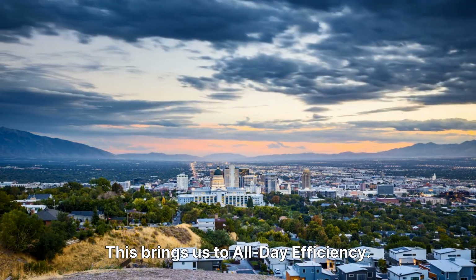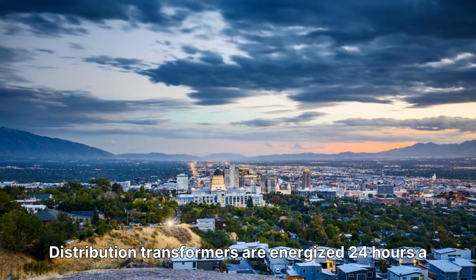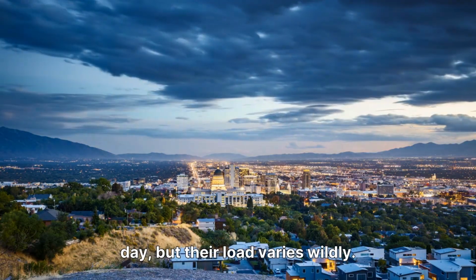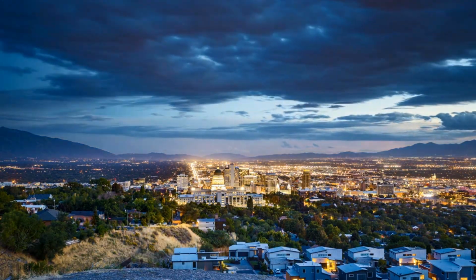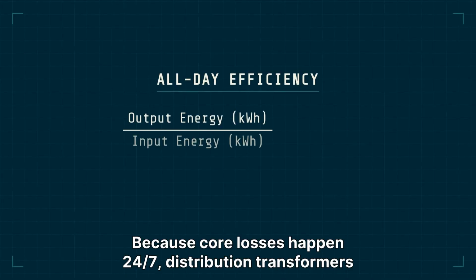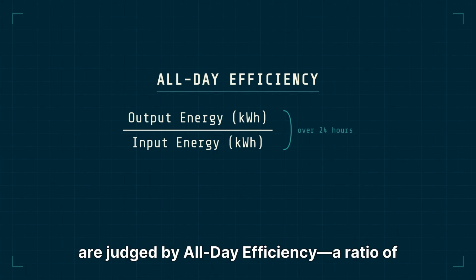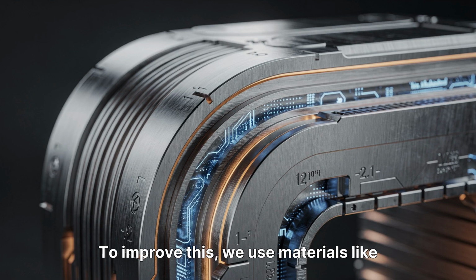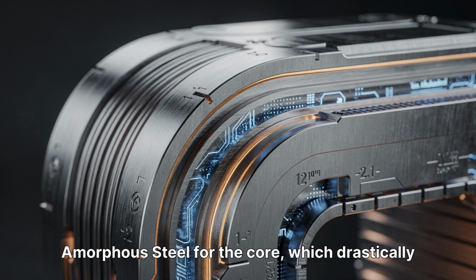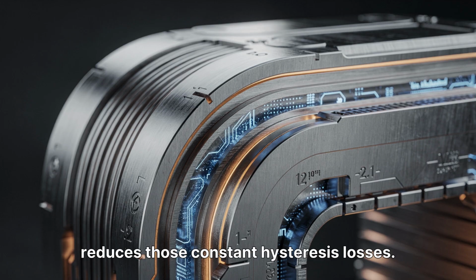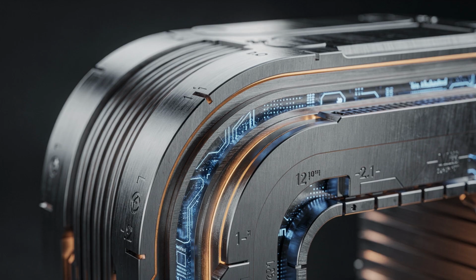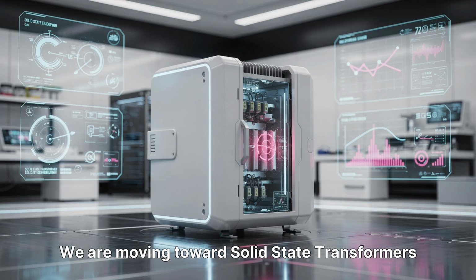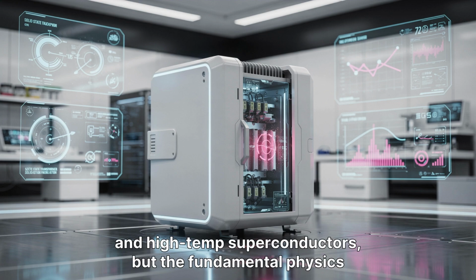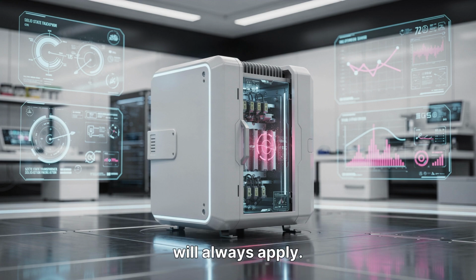This brings us to all-day efficiency. Distribution transformers are energized 24 hours a day, but their load varies wildly. Because core losses happen 24/7, distribution transformers are judged by all-day efficiency, a ratio of energy, not power. To improve this, we use materials like amorphous steel for the core, which drastically reduces those constant hysteresis losses. We are moving towards solid-state transformers and high-temp superconductors, but the fundamental physics will always apply.